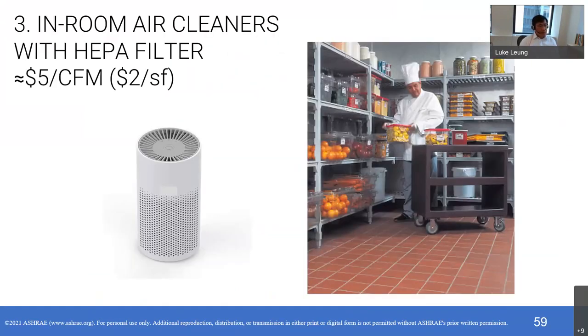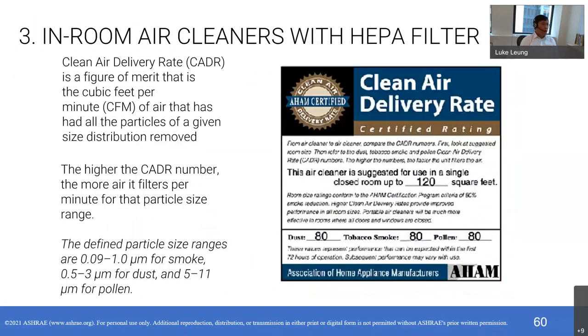If you look at the air cleaner, it's about $5 per CFM or $2 per square foot with our data point. This is a commercial building with roughly 25,000 square feet of floor plate in a floor. So it's actually quite expensive compared to the filter. Next slide. One of the reasons it's expensive is the clean air delivery rate: in this case, you can see it only covers 120 square feet. So you're going to need a lot of these to cover a 25,000 square foot floor plate. Next slide.